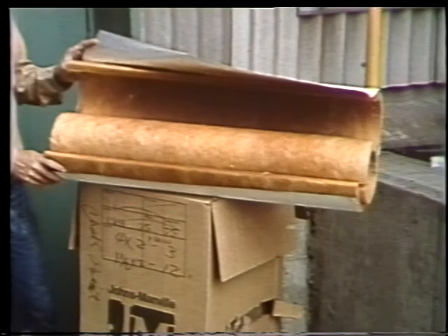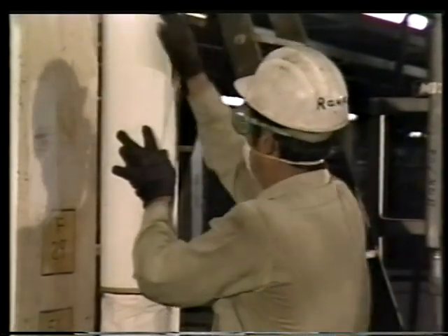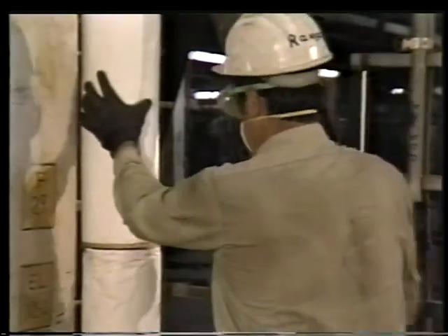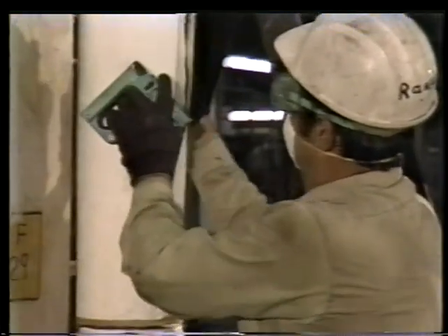The new fiberglass insulation comes in preformed pipe sections with seams along the length where the insulation opens up. One side of the seam laps over to hold the insulation on the pipe. The lap seam is stapled all the way up. The staples should be spaced about 6 inches apart, approximately 15 centimeters. The end joints are sealed with tape to prevent heat losses through the cracks between sections. The ends of the tape are stapled to make extra sure it'll stay on.